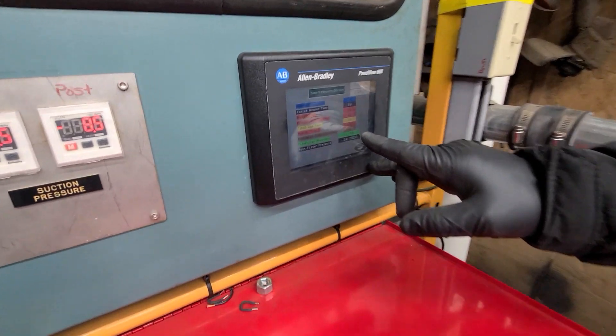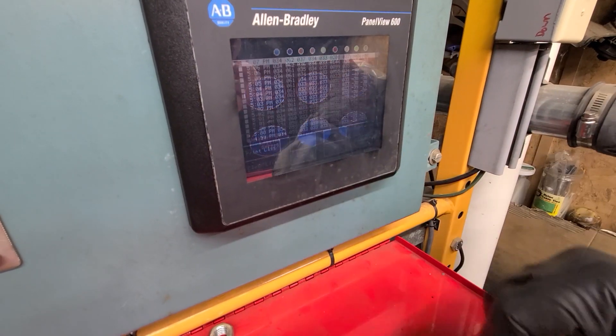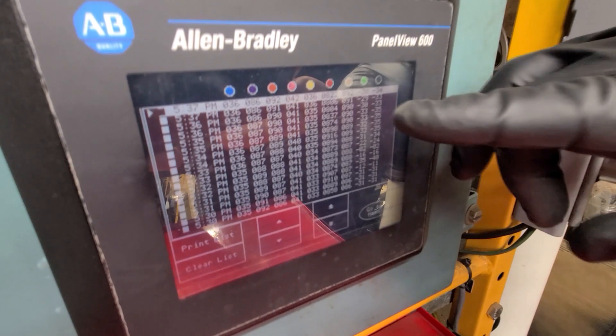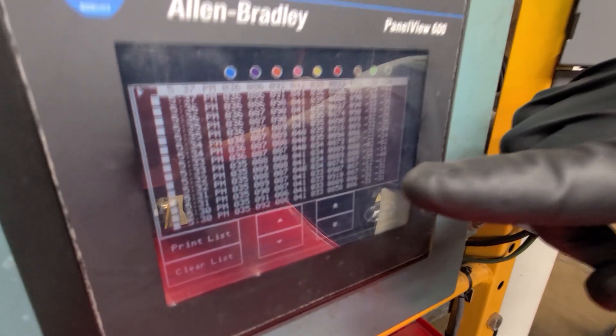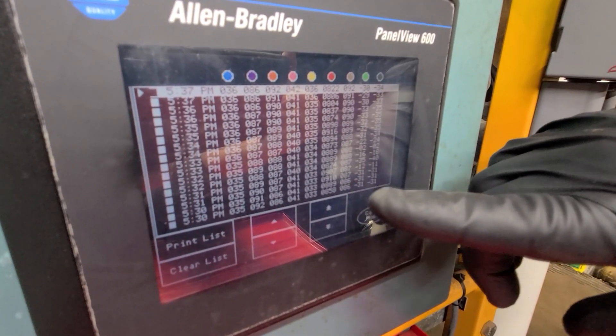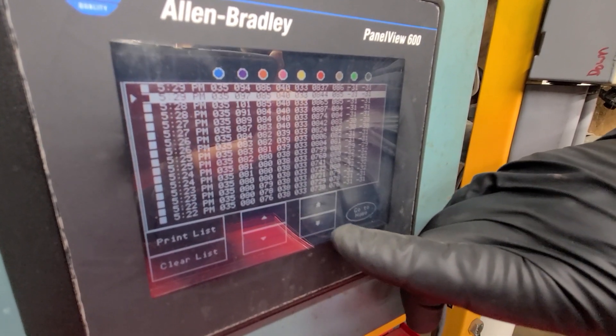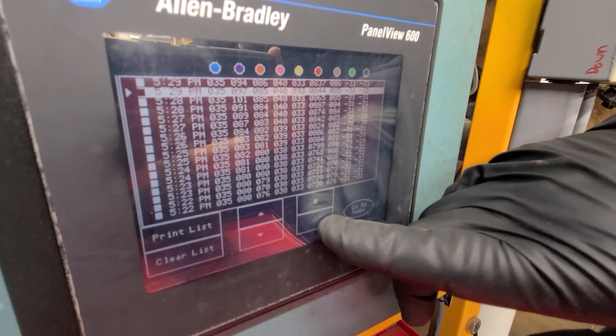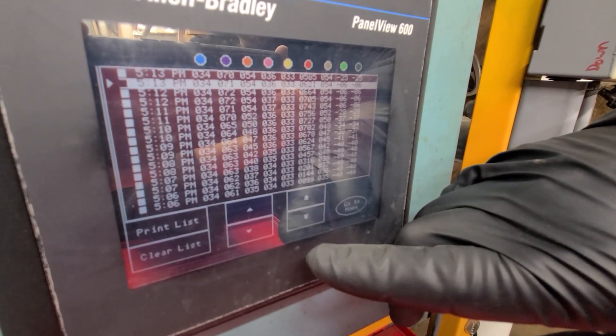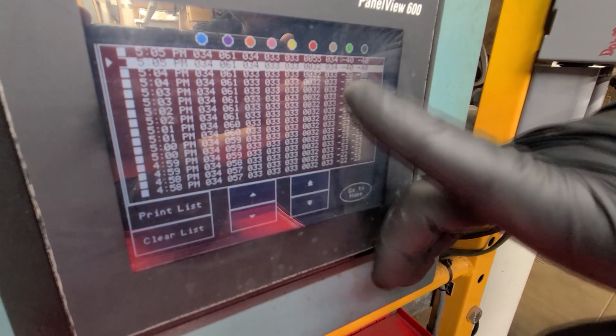We're at 820-some degrees for the hearth temperature. We're going to go to our data logging screen. Since we have some data here we'll do some entries. You can see we're up and down a little bit depending on when it shakes — 822. They've been all time stamped on the left. The 874, we were up to 910 at one point. We started at 32 degrees.